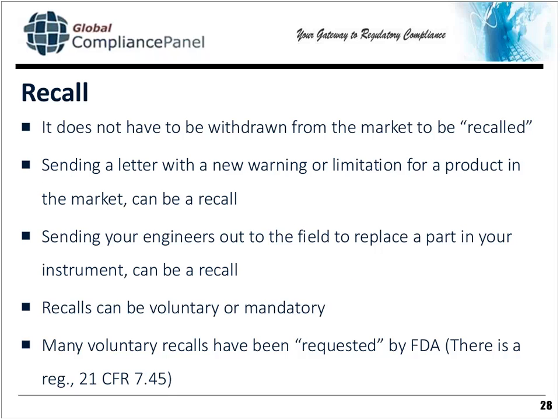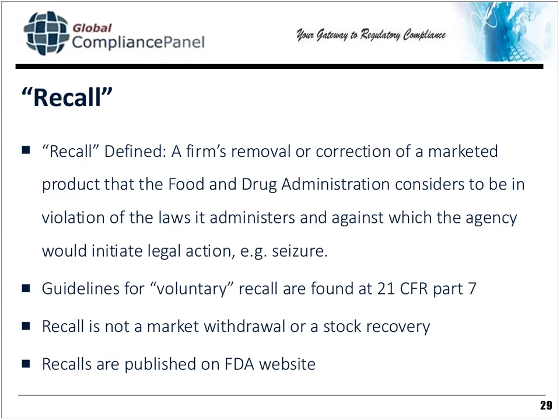Okay. And here is where it's defined. It's a removal or a correction that the Food and Drug Administration considers to be in violation of the laws, and against which the agency would initiate legal action. Guidelines for voluntary recall, not regs, are found at 21 CFR Part 7. And they are guidelines, even though they're in the regs. They say they're guidelines. It's not a market withdrawal or a stock recovery. That is to say, recalls are not a market withdrawal.